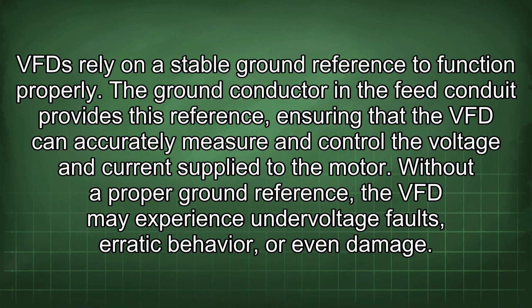VFDs rely on a stable ground reference to function properly. The ground conductor in the feed conduit provides this reference, ensuring that the VFD can accurately measure and control the voltage and current supplied to the motor. Without a proper ground reference, the VFD may experience undervoltage faults, erratic behavior, or even damage.